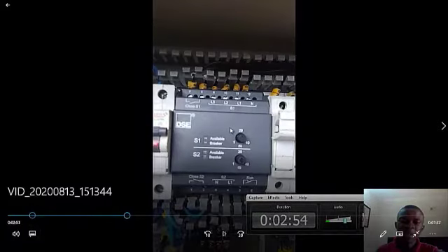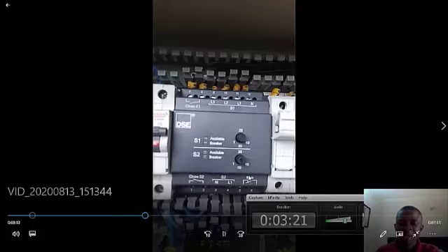This Deep Sea you see here, on this upper side you have line 3, line 2, line 1 and neutral. This is always the public source of power. Then this is a contact of this source of power. Then this is the generator source of power. Then this is the contact, and this is the run relay, which shows you that one of them has been closed.